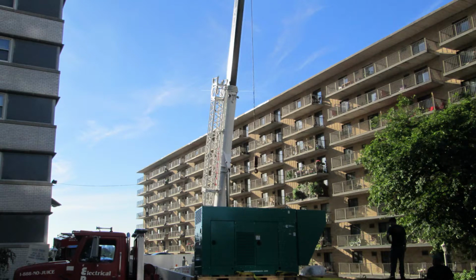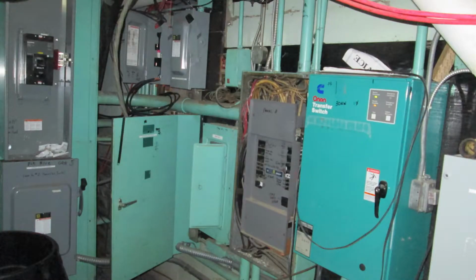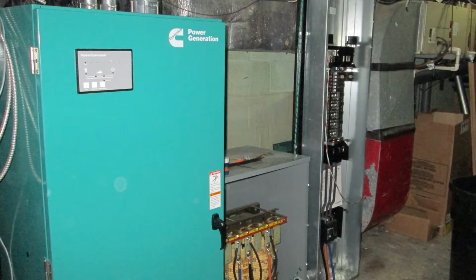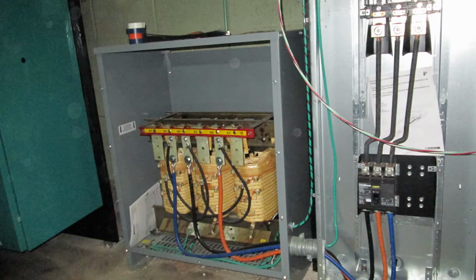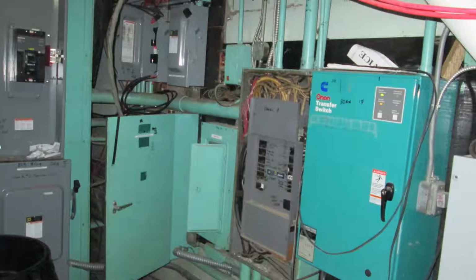In the electrical room, we had to install a new 400 amp main breaker, a transfer switch, an emergency distribution panel at 120/240, and then a transformer to make that into 208, and also a 120/208 volt panel. Little congested in the electrical room, but we were able to find a way to get all of this equipment in and meet all of the requirements of the National Electrical Code.